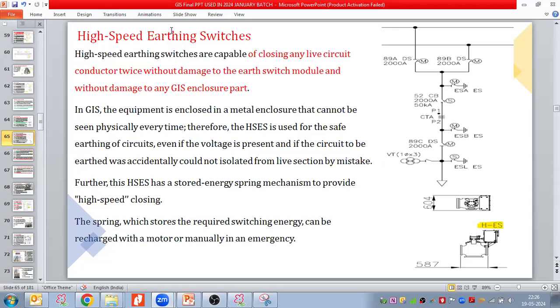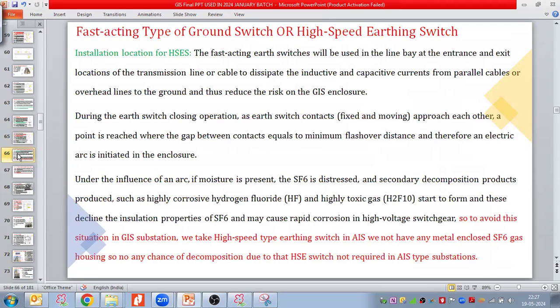We have to open the breaker, right? We have to open the disconnectors. And once the disconnector is open, then we have to close the earthing switch. Now this earthing switch or equipment closing you can do locally or by remote using the VCU and SCADA. Okay. Sir, it is written here, capable of closing any live circuit conductor twice.